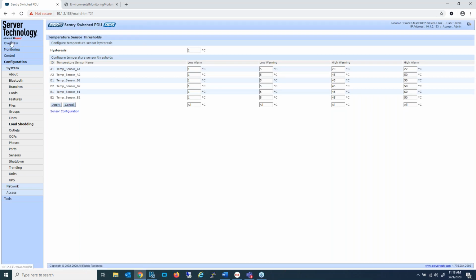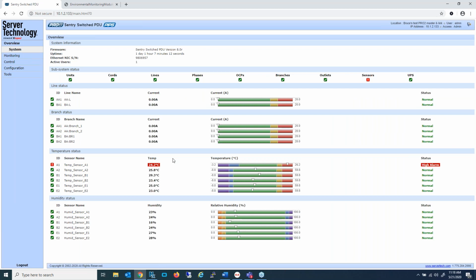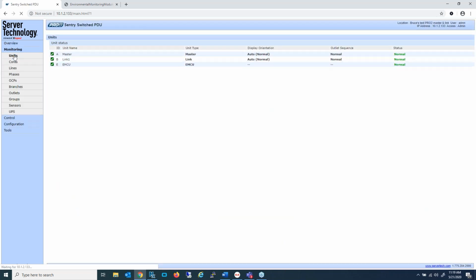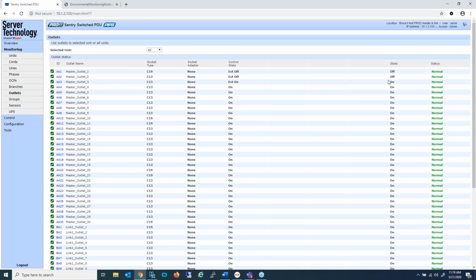Take a look at the overview first. We can now see that temperature sensor A1, the first sensor on the master unit, is in a high alarm state. And if we take a look at the outlets, we can now see that outlet number 1 and 2 are off. They were previously on. Outlet number 3 is now on. It was previously off. And as we can see over here, it was due to an event.